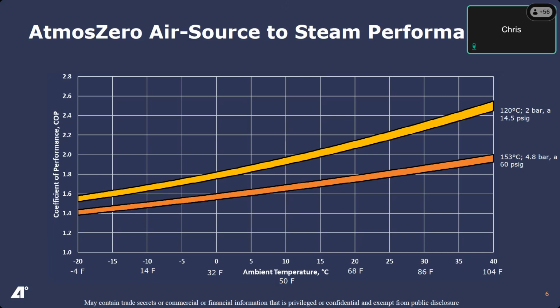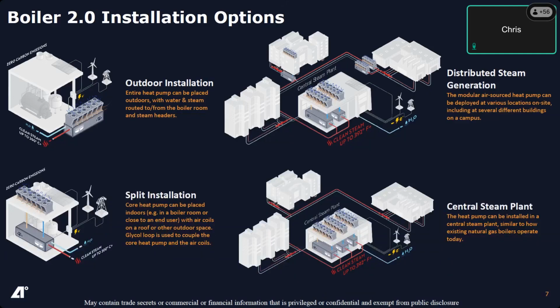You can jump to the next slide, please. Installation options. So most of our customers are looking at that top left outdoor installation. They keep existing assets in place, and they're trying to reduce Scope 1 emissions with heat pumps. It kind of is a good option for also lowering steam costs, because you can arbitrage around demand periods, and you can arbitrage around renewables or any carbon metrics that you might get from the grid by having both assets in place. Plus you have the reliability of gas as a backup. And again, that's probably 75% of our current projects are looking at outdoor installations like that, to where we're just putting 3 pipes through the wall: electric, feed water, and steam.